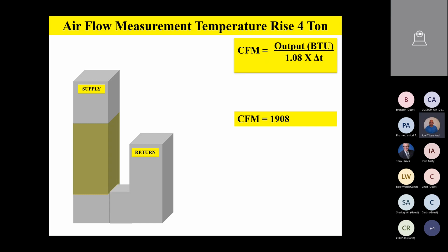And you're on high speed tap, and when you commission the unit, when you start it up, you notice that you've got 1900 and change for CFM. Well, you need to slow it down. So maybe you'll have to go to a medium high or maybe even medium speed on that particular duct system to give you your 1600 CFM or close to 1600 on that 4-ton unit.